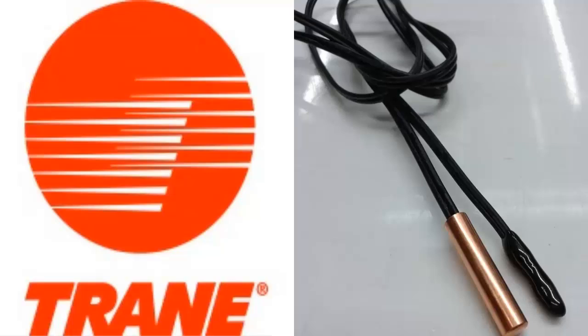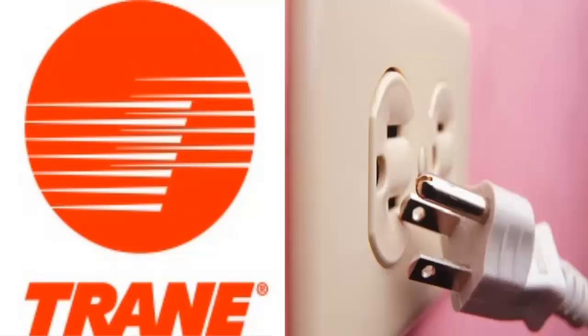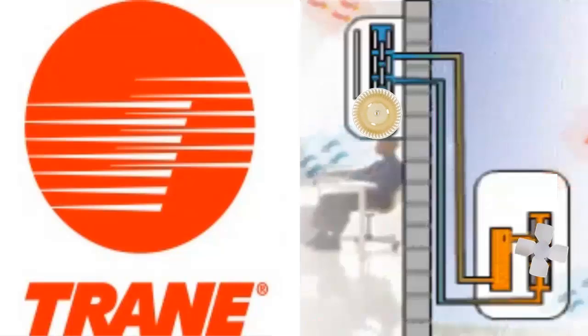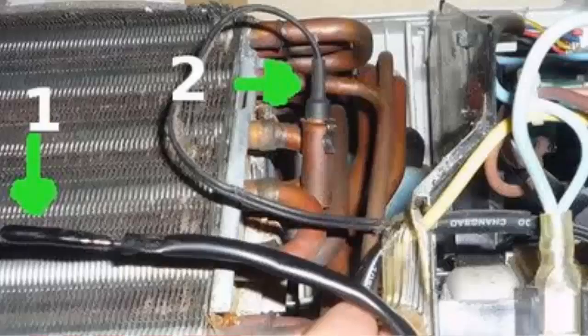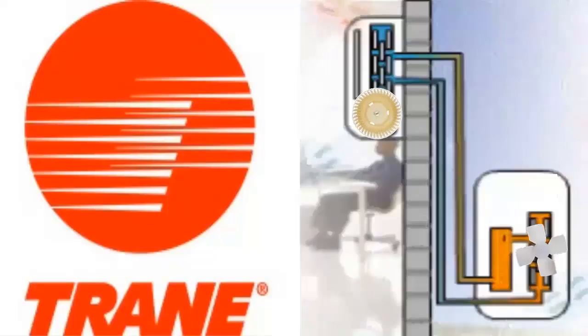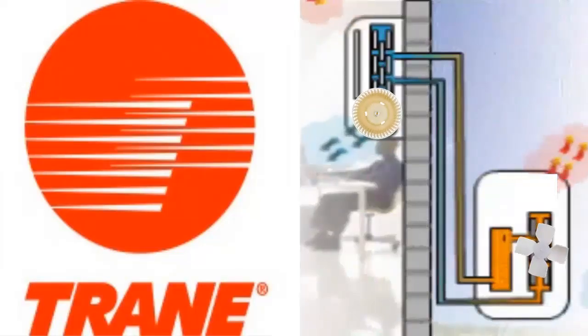A. Disconnect the equipment from the power for several minutes. Then, turn on the equipment and check if the fault code persists. B. Visually inspect the position of the temperature sensor. C. Visually check the connection of the sensor and its connection to both the external and internal electronic modules.